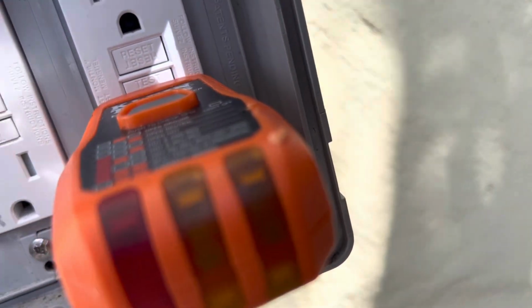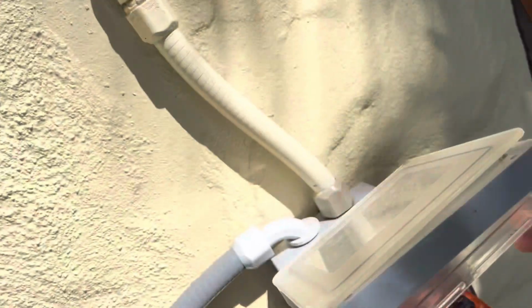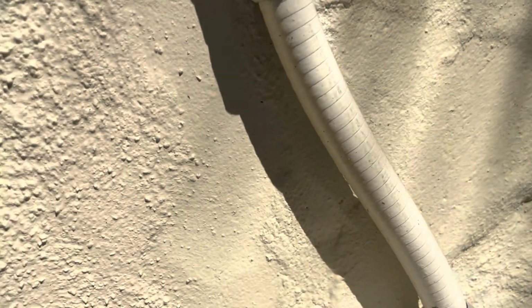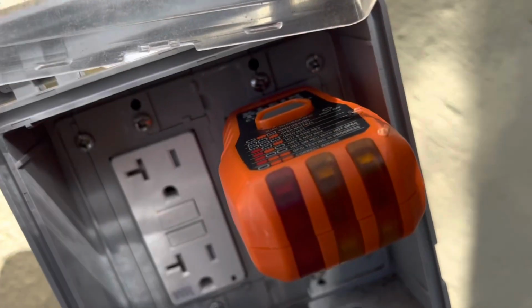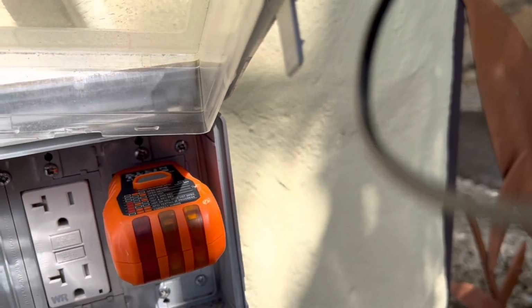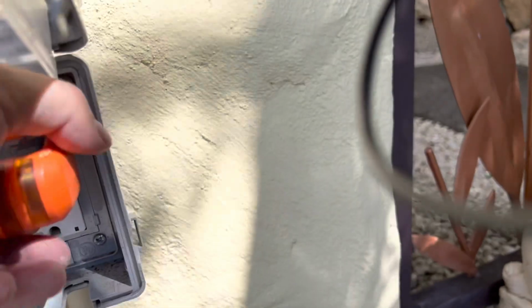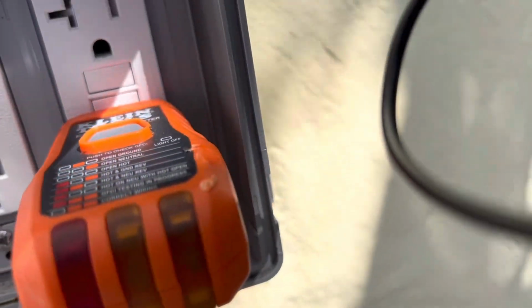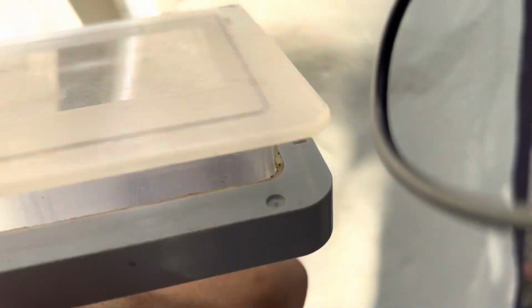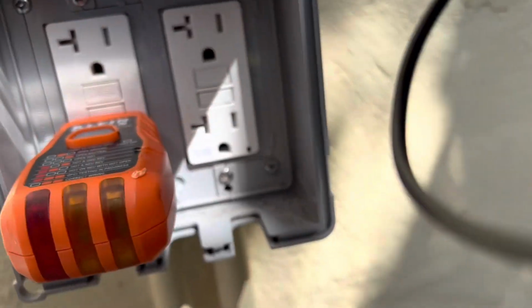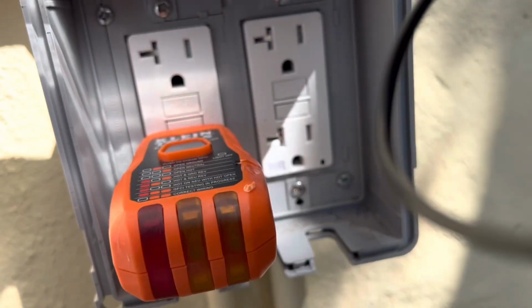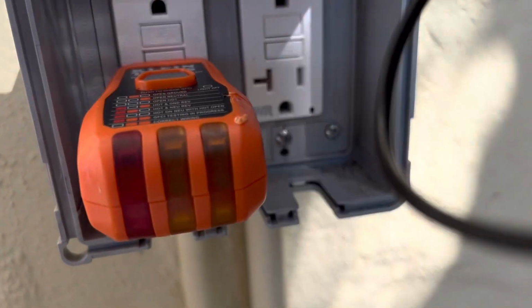It's giving me one amber light. One amber light means open ground—not good. The bottom one, same thing: open ground, not good. And this one on the left has no power to it at all—that's a dud. So something's going on: we've got a ground open somewhere, which can be tricky to diagnose, but let's check if any breakers have tripped first.